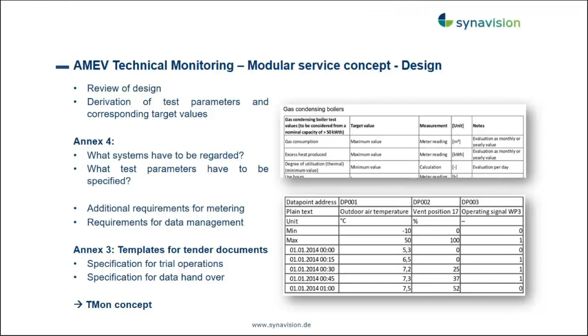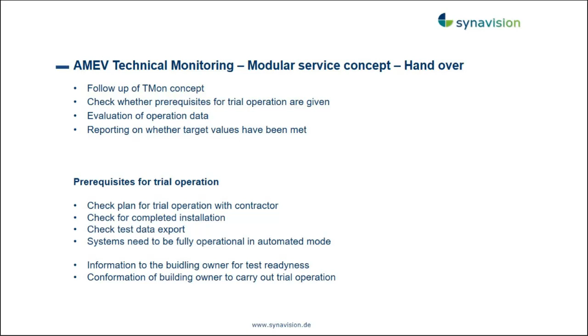Okay, so basically this is the general idea of the process. There's one aspect you can define in addition when you do this kind of service: you can define typical actions that should be done within the trial operation. I said it's automatic mode - yes, it is automated mode, but of course you can ask for certain changes. You can, for example, provide a schedule that says, within our 2 weeks of trial operation, I want some characteristics to be changed, some schedules to be changed. Maybe you can just unplug a sensor and see whether the system reacts as it's supposed to.